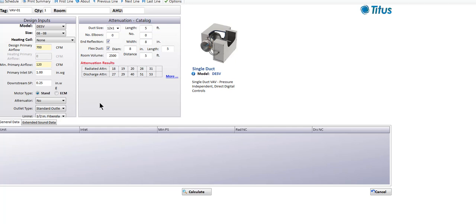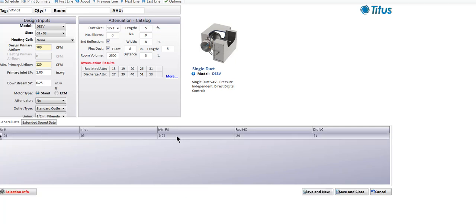We'll go ahead and make our selection with standard half-inch fiberglass lining and hit Calculate. It gave us a size 8 box with a minimum static pressure drop of 0.02 inches — meaning it takes 0.02 inches of static pressure to move 700 CFM from the inlet to the outlet with the damper wide open. It also gives us our sound levels: a radiated sound level of NC24 and a discharge sound level of NC31.